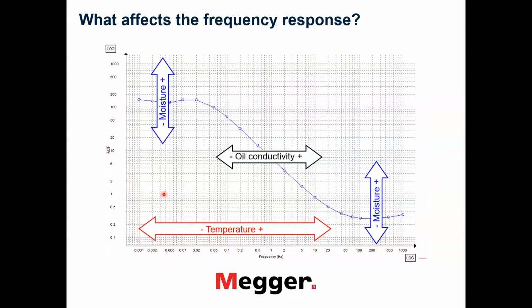And the effects of moisture are at both ends. This end goes up and down depending on moisture content, as well as this end goes up and down, and oil conductivity will influence the curve shape in the middle. The lower conductivity will make the curve go like this, and the higher conductivity would make the curve go like this, and then make some dips and stuff.